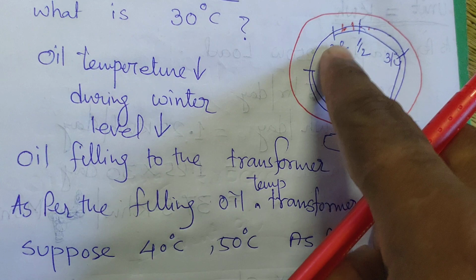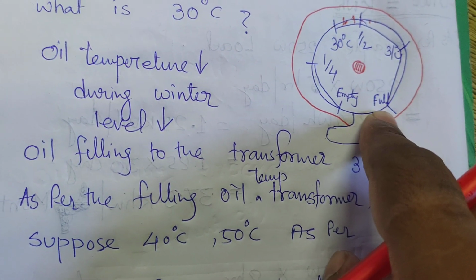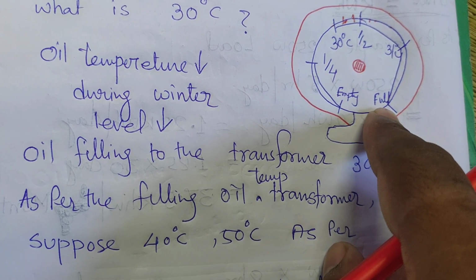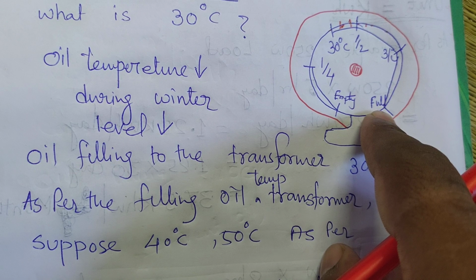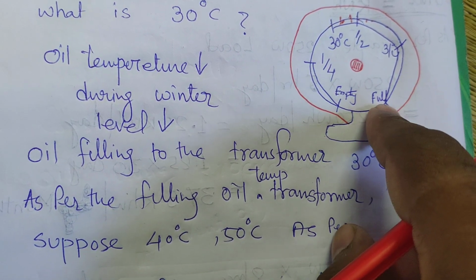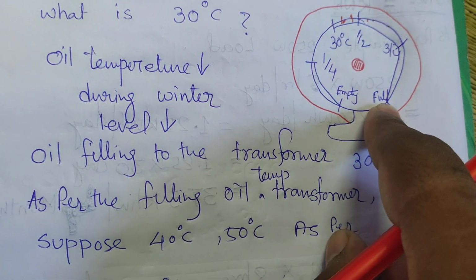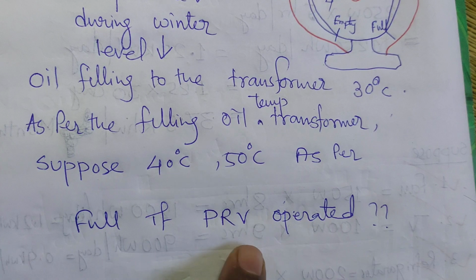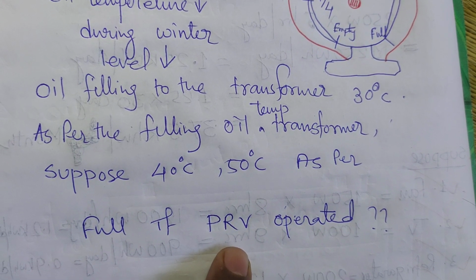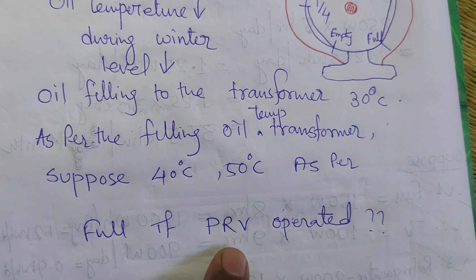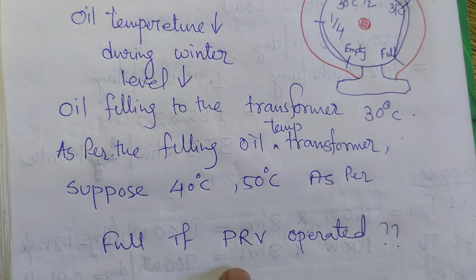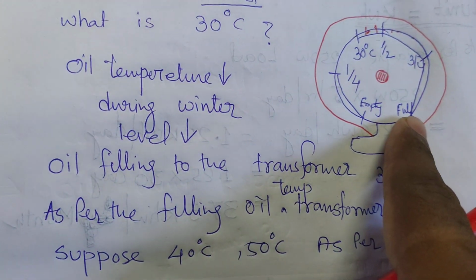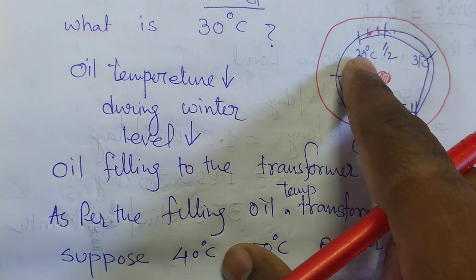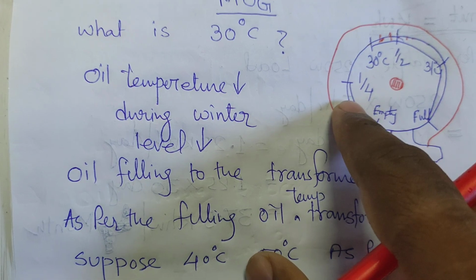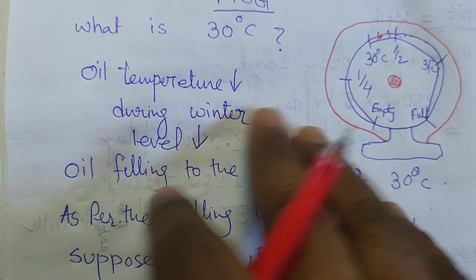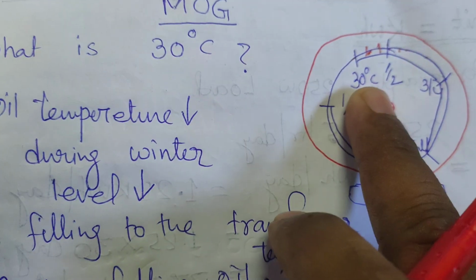If you fill the transformer oil up to full, what will happen? If the transformer load increases, the heat of the oil will increase. That means expansion of the oil. If the oil does not get any expansion space or free space, it will operate the PRV, the pressure release valve, and if the pressure release valve operates, that means unwanted tripping of the transformer will occur. So you should remember: do not fill the transformer up to full. You must fill it up to 30 degrees, because the inside temperature and the 30 degree mark are related to each other. So filling the conservator oil up to 30 degrees is very important.